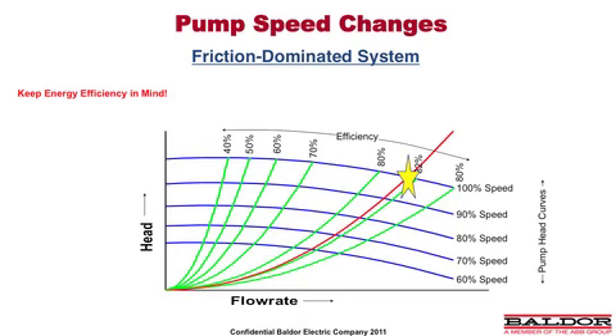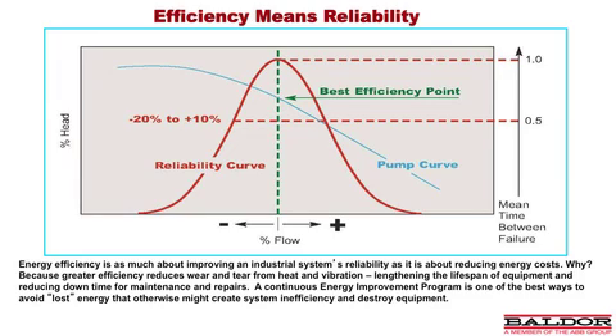trip on high amps. With the controlled start methodology, we are able to control the speed of the pump and bring the pump up without overloading and creating recirculation within the pump by slipping the clutch and controlling the speed of the pump. And you'll note, by doing so, as we ramp up the pump, following the red system curve line, you will see that the pump maintains its best efficiency point throughout the startup process. So, by maintaining that efficiency, it means reliability. Efficiency and reliability complement one another.